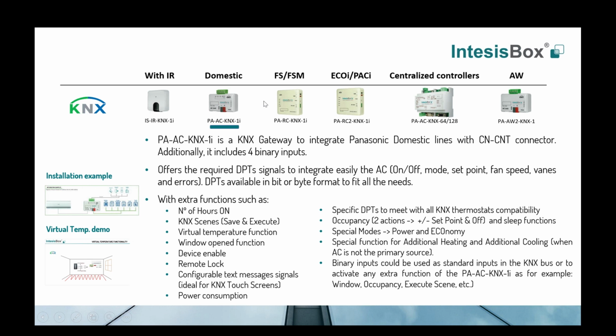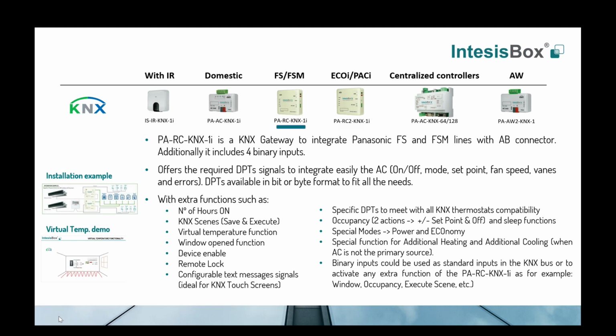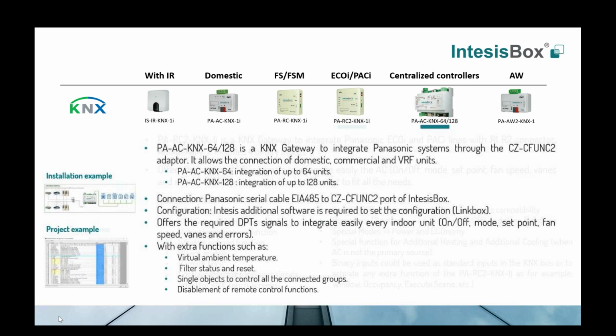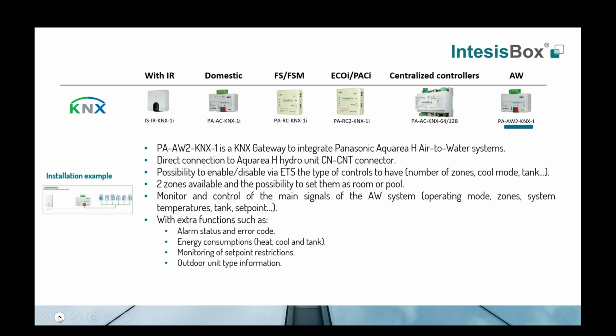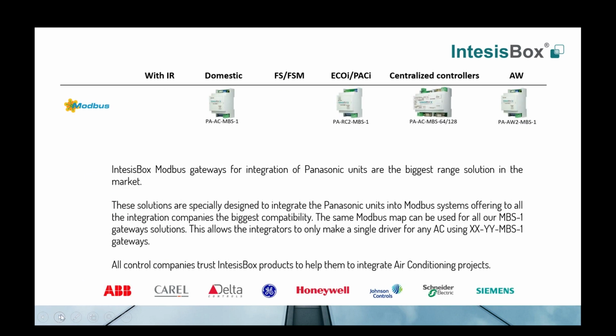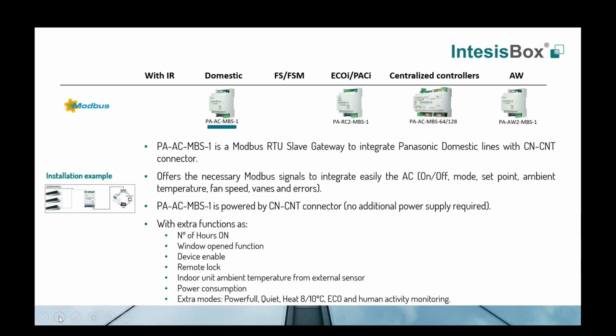Then comes this one here. This is our BACnet gateway, KNX gateway. I'm not going to talk too much detail about this, because this is just to show you that we have the tools, the devices, all kinds of controls to talk to our indoor units. So if you have a job where you have installed our residential units in a commercial application, no problems. And if they need a BACnet device, our units talk BACnet IP, BACnet Modbus, BACnet MSTP, you name it.